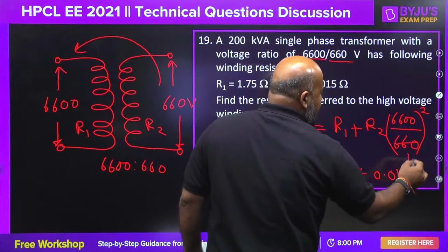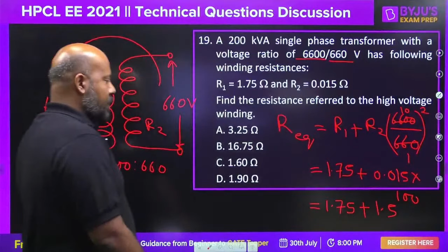Now you have to write the high voltage side turns ratio, where you are going. High voltage side is 6600. Square it. R1 is given as 1.75, plus R2 is 0.015, multiplied by 100, so this is 1.75 plus 1.5. Add it up, it comes to 3.25.